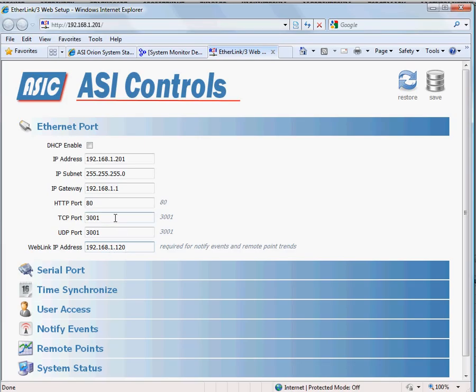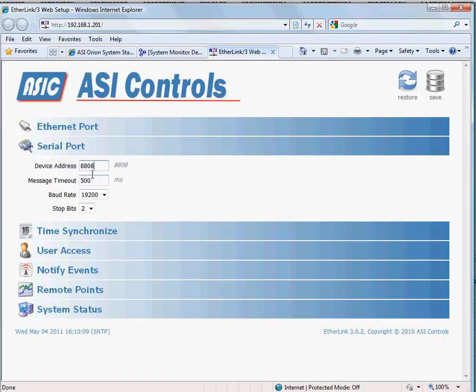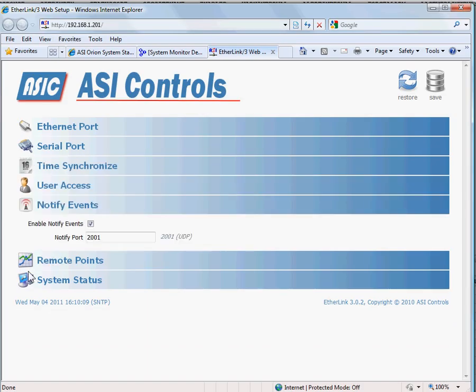The communication to the local controller gives us the device address. We'll use that later in expert, talking at 19.2. Also important to enable the notify events. That has to be checked. We're using the standard port 2001.